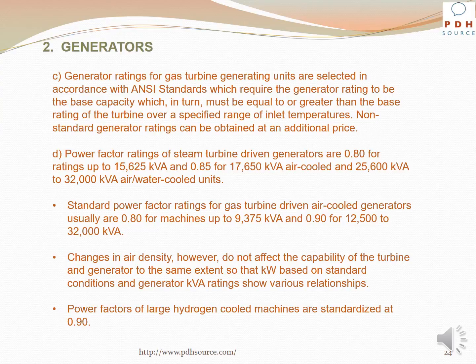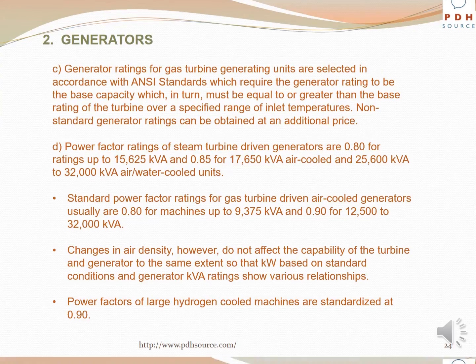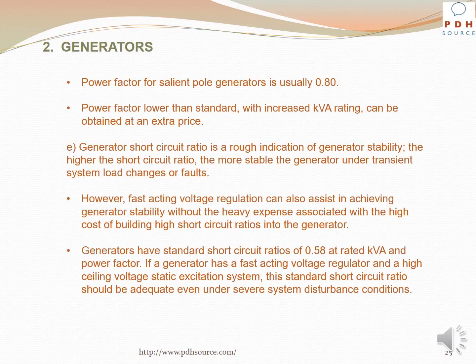Changes in air density, however, do not affect the capability of the turbine and generator to the same extent that kW based on standard conditions and generator kVA ratings show various relationships. Power factors of large hydrogen-cooled machines are standardized at 0.90. Power factor for salient pole generators is usually 0.80. Power factor lower than standard with increased kVA rating can be obtained at an extra price.